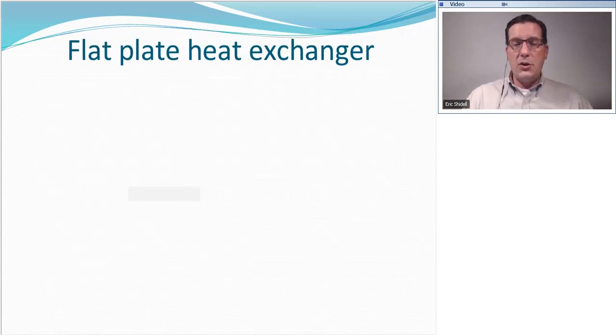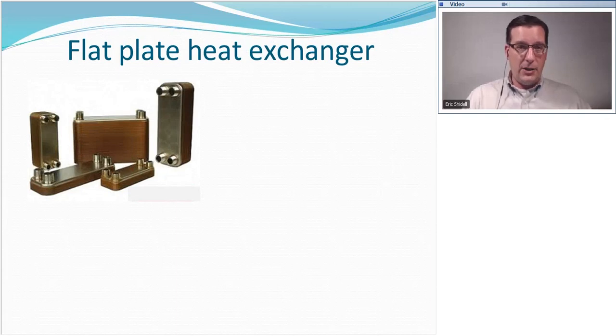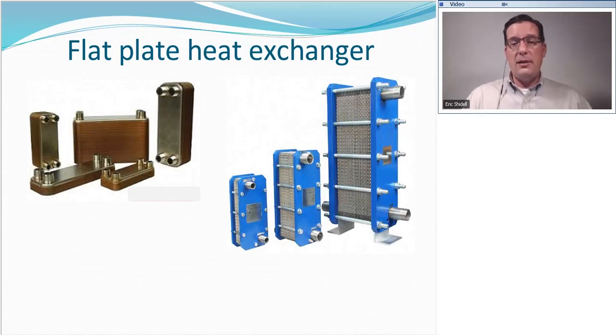Another version of a water-to-water heat exchanger is called the flat plate heat exchanger. It's also known as a brazed plate heat exchanger. In fact, flat plate and brazed plate are sometimes used interchangeably, but there is actually a difference. These critters on the right are what are called flat plate. They are rebuildable, they are cleanable, and they are repairable. These are called brazed plate, and they are not cleanable or repairable.